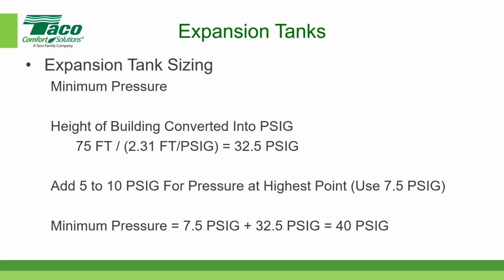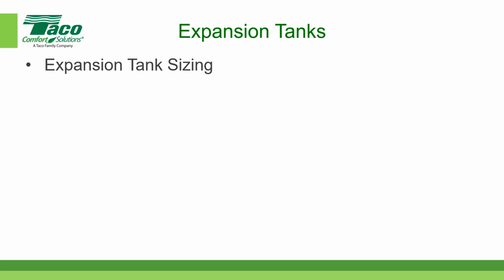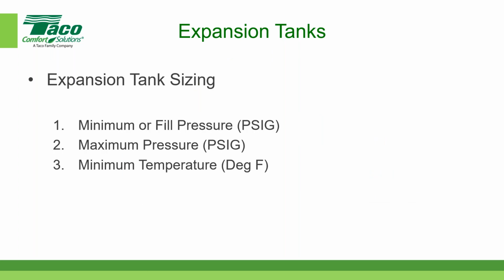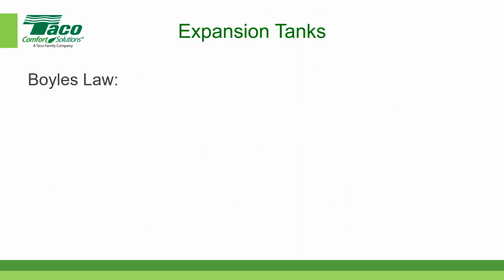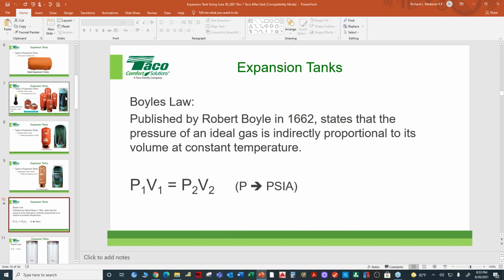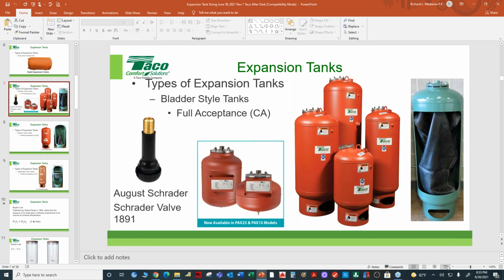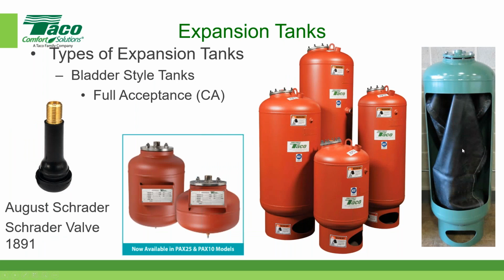What is the best way to test the bladder, if the bladder has leaks, or the condition of the bladder? Let's go back to our little cutaway here, which will demonstrate this. There is our cutaway on the right side, the photograph. If for some reason the bladder should fail, water will leak from the bladder to the air side of the system. Eventually, over time, the air that's trapped inside the steel container will go into solution, especially if the system has been running for a while.